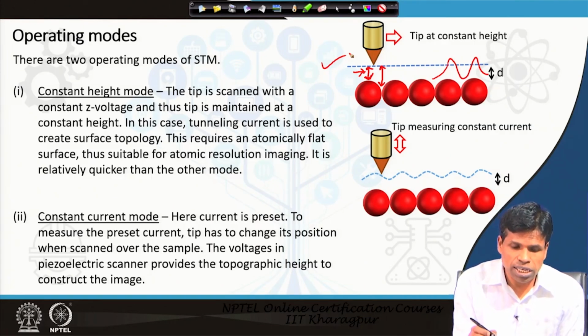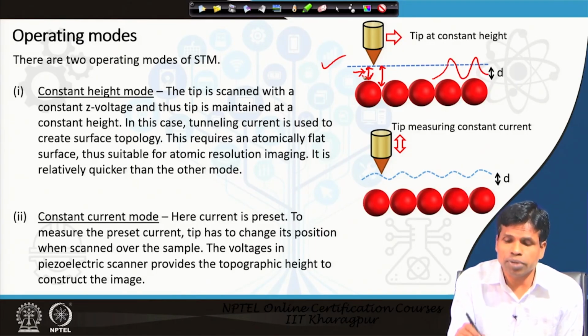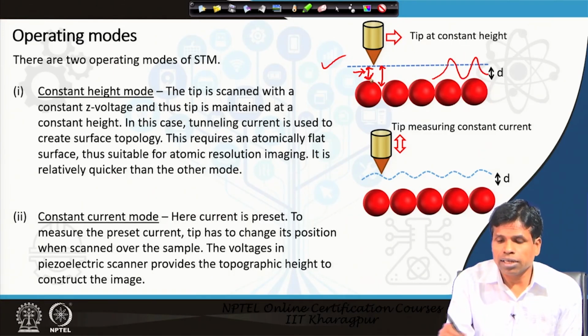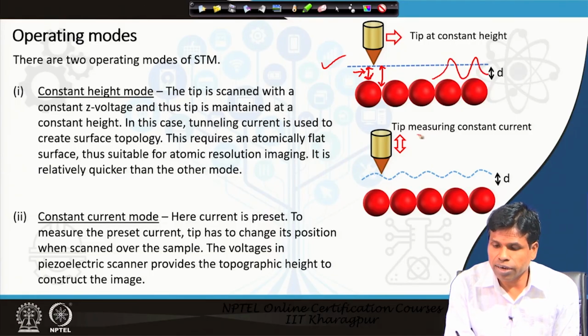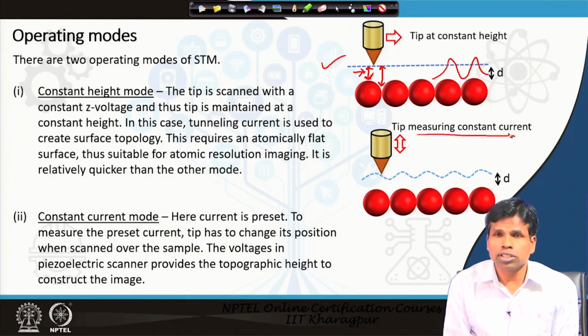And this mode can provide atomic resolution images, because we directly measure current at the level of picoampere to nanoampere, and thus it can give us very high resolution. And another mode is the constant current mode. Constant current mode is used for an unknown sample or a rough sample.